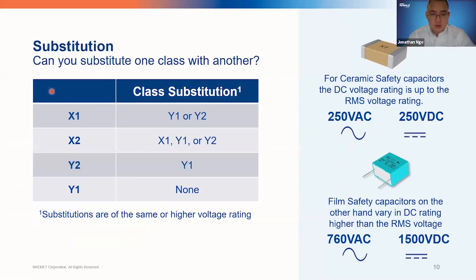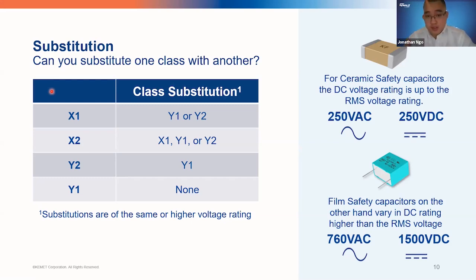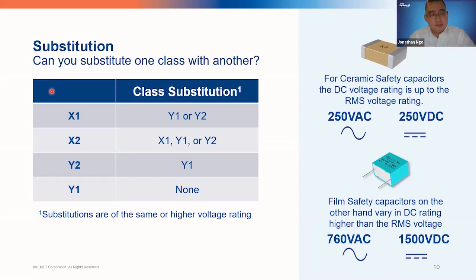On substitution — we get this question quite a bit. Can you use a Y capacitor in a line-to-line or line-to-neutral application? The answer is yes. Y capacitors have extremely high impulse ratings, so you could potentially use them in substitution for an X1 or X2. However, it's not as efficient because Y capacitors have to be conservatively designed and are generally larger because of that. So if you're concerned about not over-speccing the part for the X capacitor location, I would definitely recommend using the correct safety rating for that location.